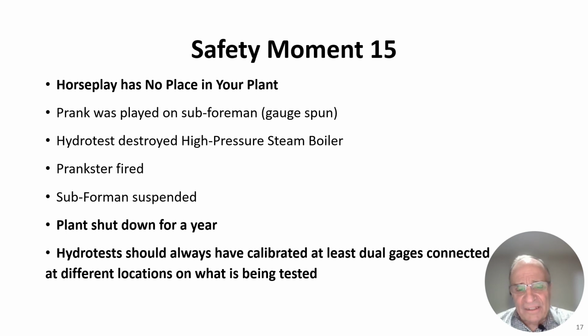And it's typical for a test like this to have an instrument person there or someone from the chem lab with a dead weight tester to confirm that these readings are correct. Because don't forget, this is a critical piece of equipment, and it's certainly a safety hazard if in fact one of those tubes had ruptured or ripped out of the steam bundle. It could have sent shrapnel across and hurt someone or even killed someone. The result of what did happen was that the piece of equipment was totally destroyed.